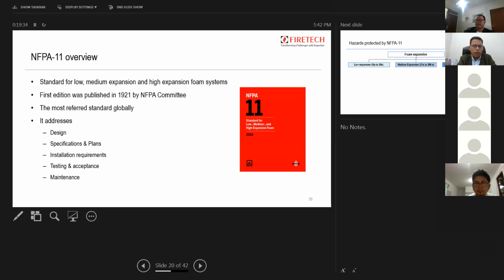Very good evening to all of you. Now, NFPA 11 is basically one of the most important standards used globally for the design of foam suppression systems. Generally, foam suppression systems are used for extinguishing combustible materials like wood and paper fires, and majorly for extinguishing oil and gas fires. So this is where this standard comes into place for designing, specifying, installation, testing, and maintenance.